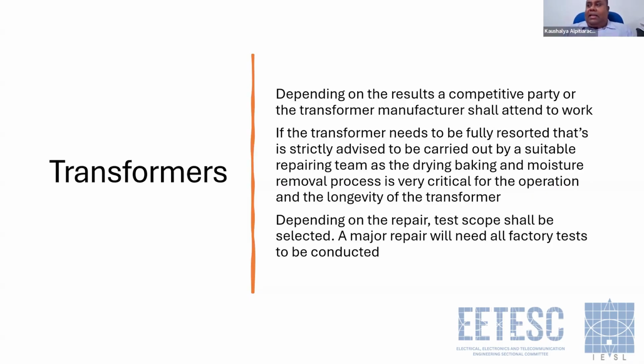If you can contact the manufacturer, that's the best. Depending on the repair, the test scope shall be selected. A major repair will need all factory tests to be conducted. You will have to check the winding; if rewinding has been done, ratio, vector group, everything will have to be checked.